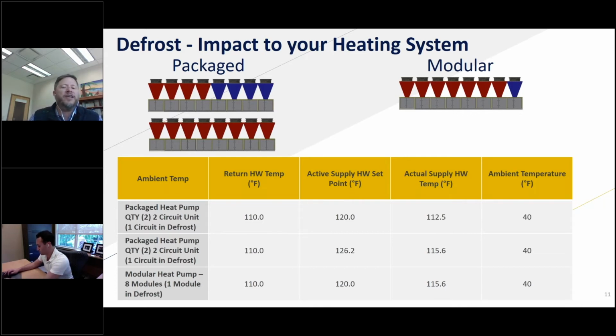What you're seeing is you either have to throw a lot more capacity at it, or you have to raise the set point of the operational units, elevating the hot water temperature that we're making, to overcome a unit or units in defrost. So again, it depends on how sophisticated your building automation system is. You have to overcome maybe multiple units that are in defrost, and that really drives what our design looks like.